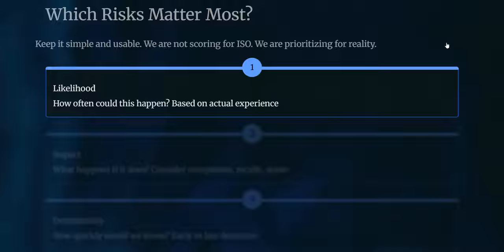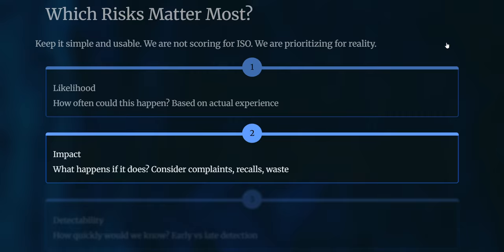For likelihood, just ask yourself: how often could this happen? And the answer doesn't need to be superficial. It has to be based on actual experience, the history in the company, the benchmark in the industry, or the publication's indication. And then we do have impact. You ask yourself, what happens if this risk really happens? And when you ask yourself that, consider the complaints that will come from it, the recall, the waste, and overall consequences. And based on that, you can assign the priority.